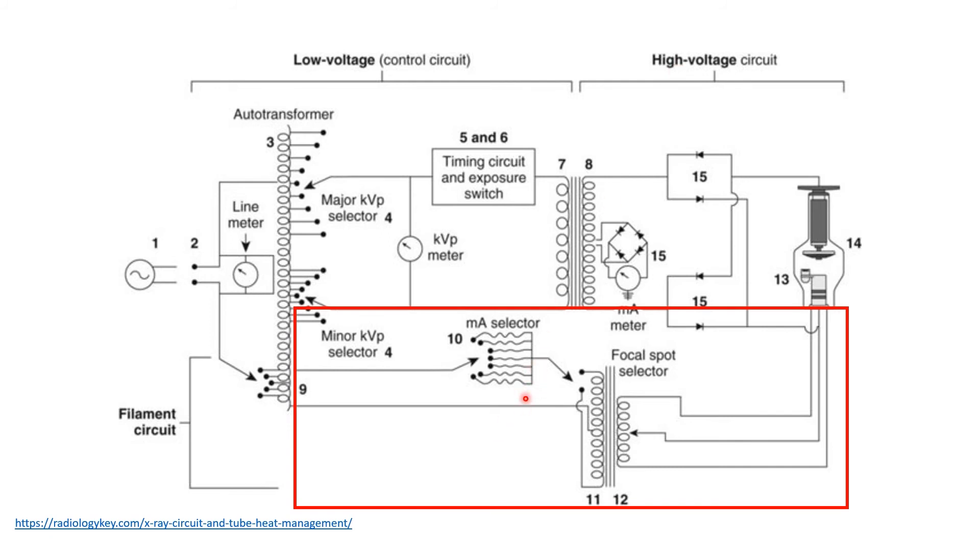The sub-circuit begins at the secondary side of the auto transformer, and the current flows from the auto transformer through the MA selector up to the primary side of the step-down transformer, and back of course to the auto transformer.